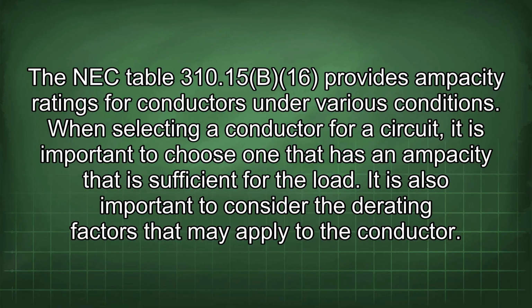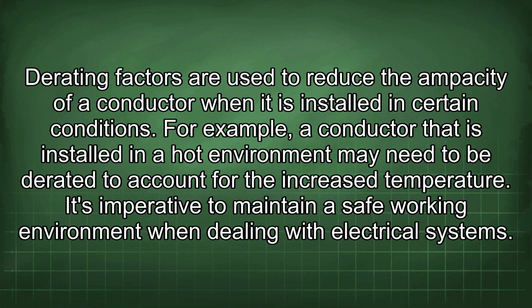It is also important to consider the derating factors that may apply to the conductor. Derating factors are used to reduce the ampacity of a conductor when it is installed in certain conditions. For example, a conductor that is installed in a hot environment may need to be derated to account for the increased temperature. It's imperative to maintain a safe working environment when dealing with electrical systems.